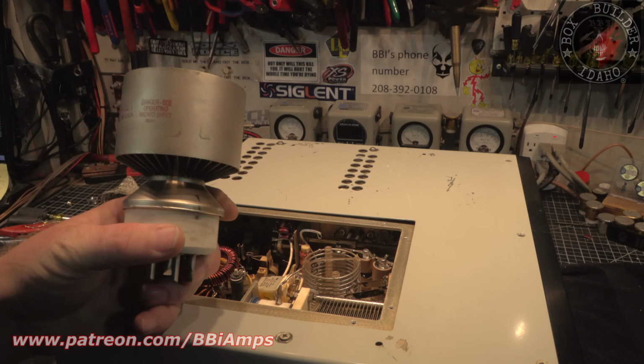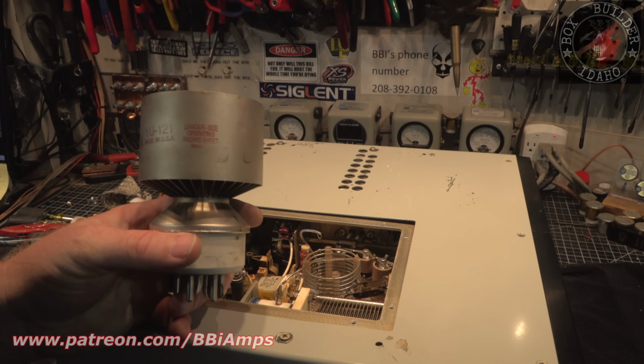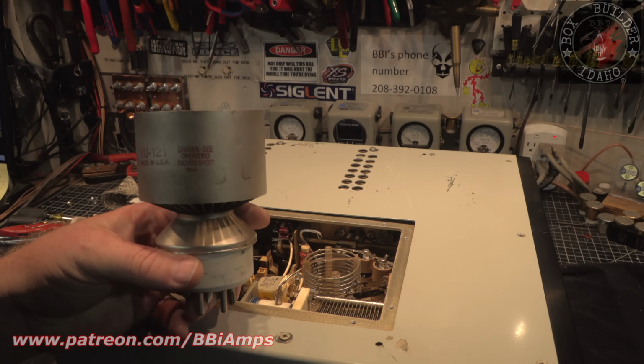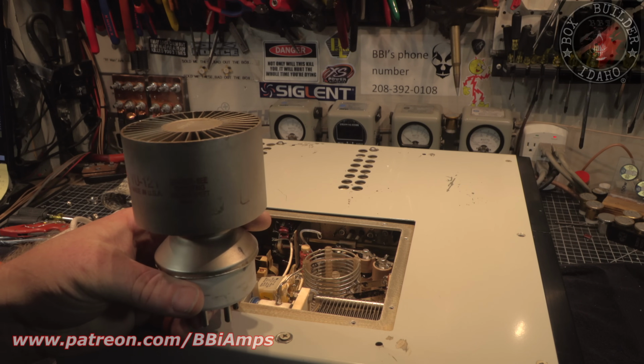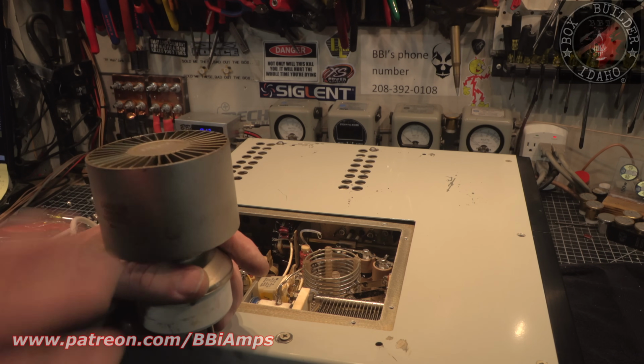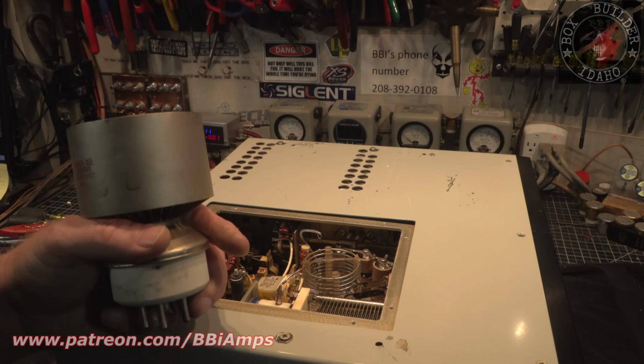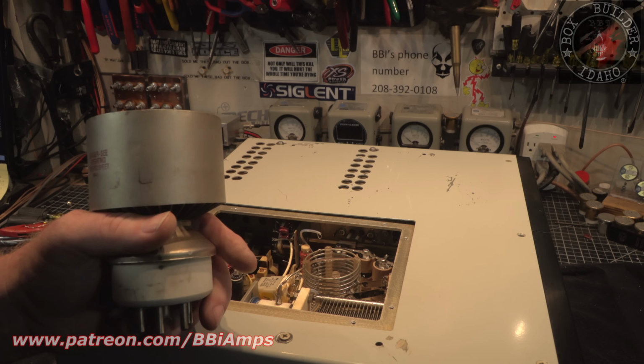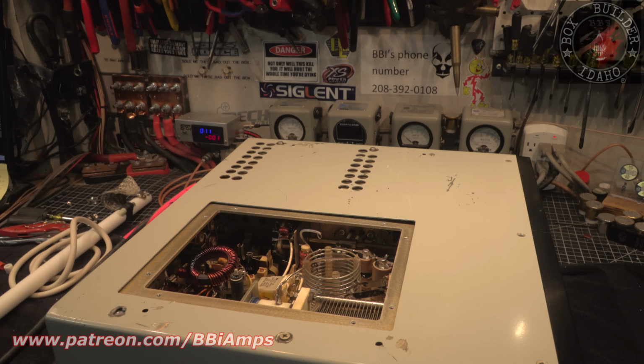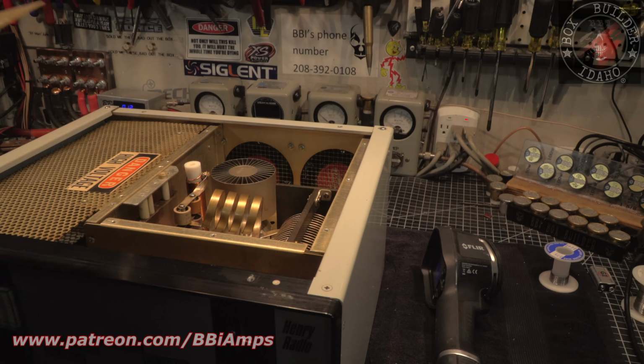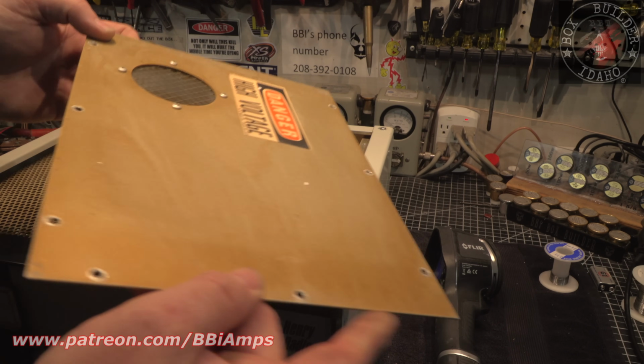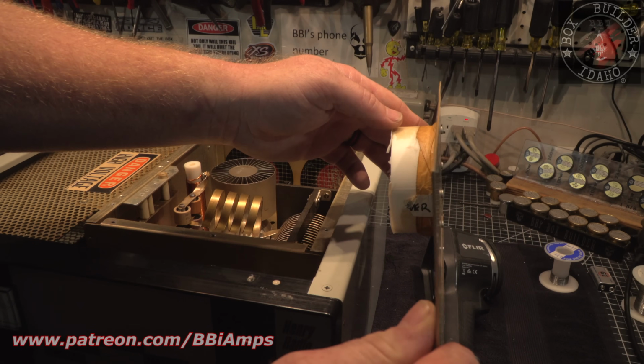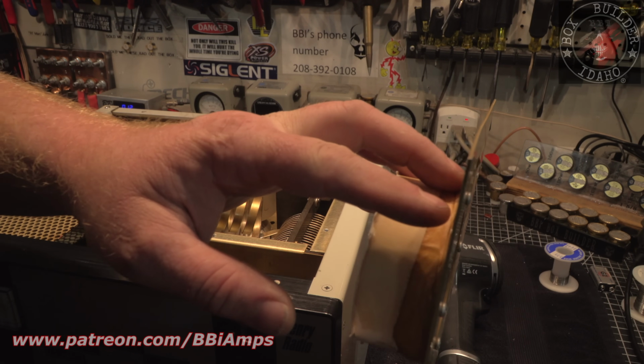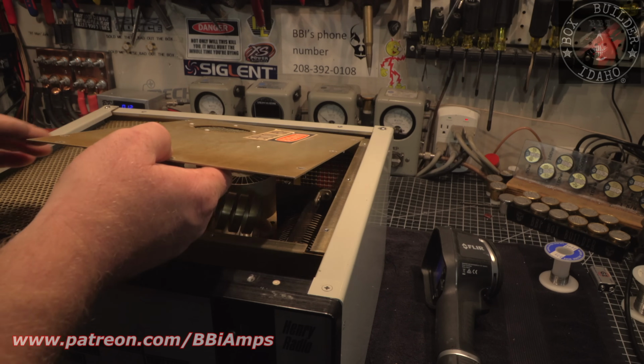I'm telling you, this is not the rarest thing on earth, but this is still pretty expensive, this tube. So we're going to set it upright. We're going to let it sit. We're going to put the rest of the air chamber on here so it's got forced air through the anode, and we're going to let it just cook all night long. Filament, no high volts. And I pray to God it's not the tube. Pray to God it's not the tube. All right. Straighten this all out. This was bent up like a taco a little bit ago.